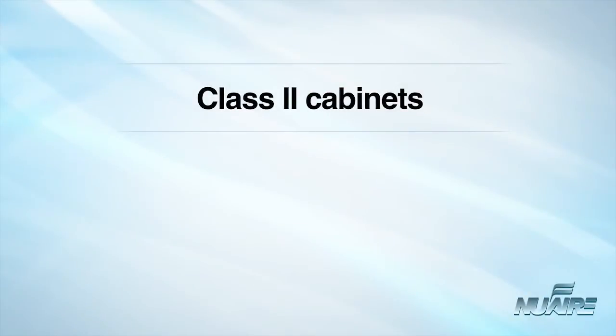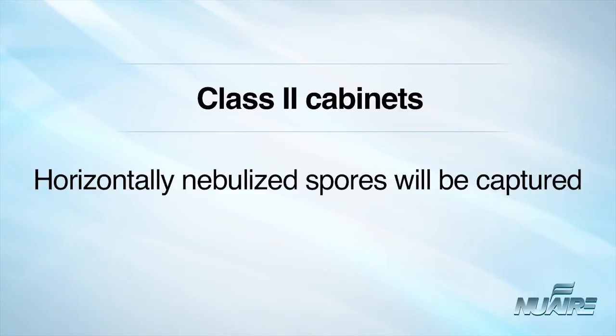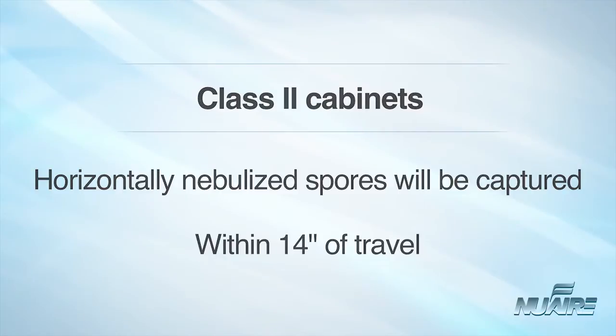Class II cabinets are designed so that horizontally nebulized spores will be captured by the downward flowing cabinet air within 14 inches of travel.